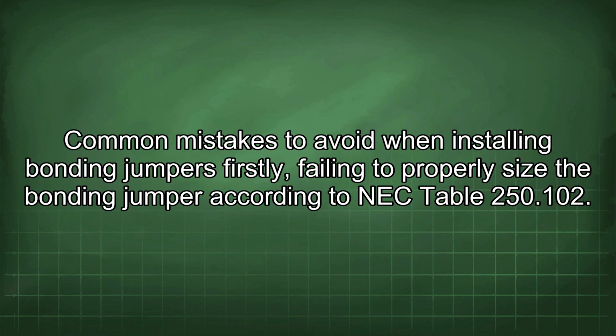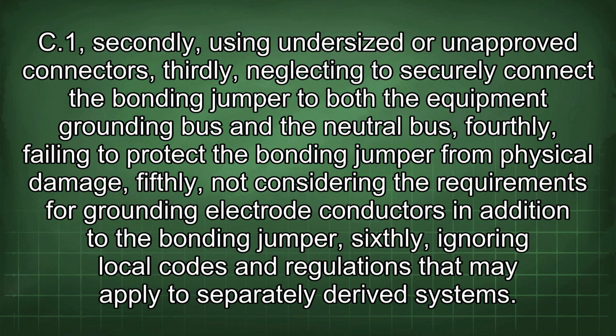Common mistakes to avoid when installing bonding jumpers: firstly, failing to properly size the bonding jumper according to NEC Table 250.102(C)(1). Secondly, using undersized or unapproved connectors. Thirdly, neglecting to securely connect the bonding jumper to both the equipment grounding bus and the neutral bus. Fourthly, failing to protect the bonding jumper from physical damage. Fifthly, not considering the requirements for grounding electrode conductors in addition to the bonding jumper. Sixthly, ignoring local codes and regulations that may apply to separately derived systems.